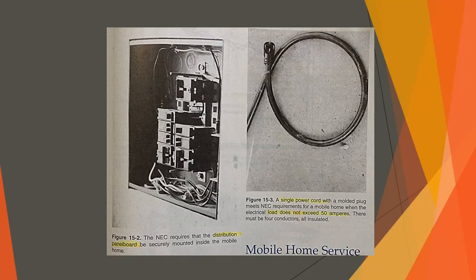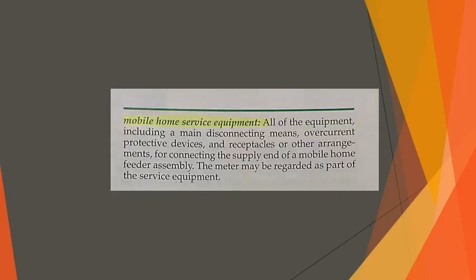The electrical feed can be supplied in any of 3 different ways. A mobile home power supply cord. This is permitted if the load is 50 amps or less. However, if the mobile home has factory equipped gas or oil heating and cooking equipment, a 40 amp cord is permitted. Figure 15-4 shows a typical installation.